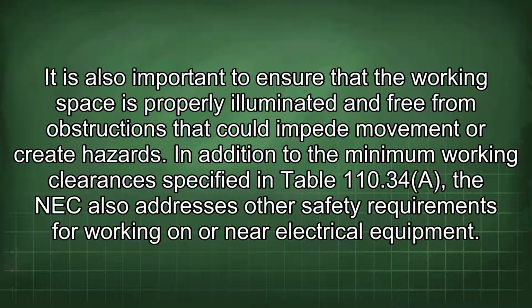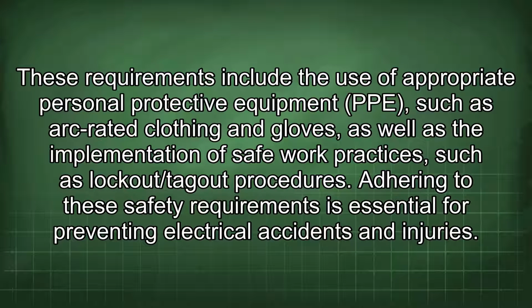In addition to the minimum working clearances specified in Table 110.34(A), the NEC also addresses other safety requirements for working on or near electrical equipment. These requirements include the use of appropriate personal protective equipment (PPE), such as arc-rated clothing and gloves, as well as the implementation of safe work practices such as lockout/tagout procedures.